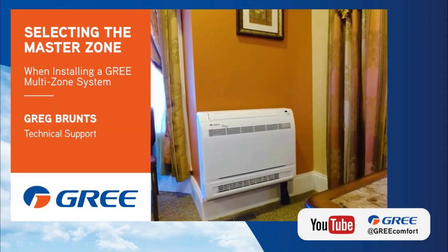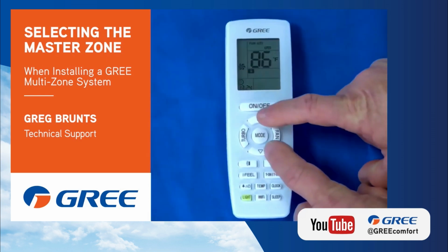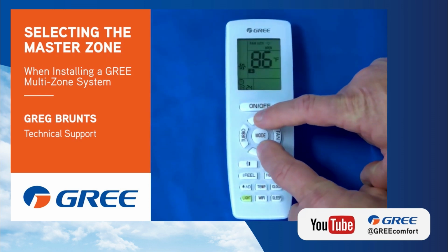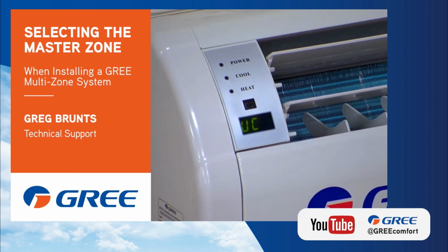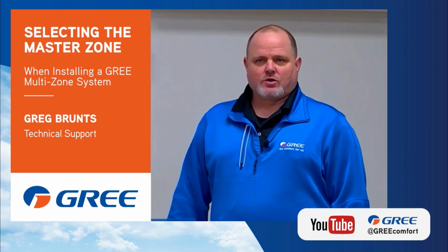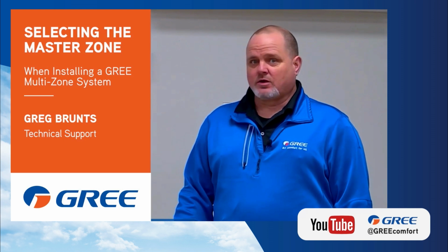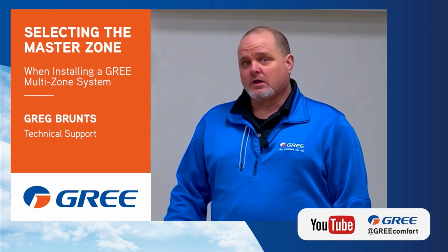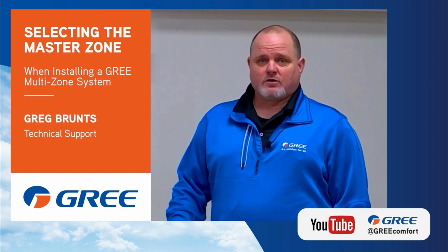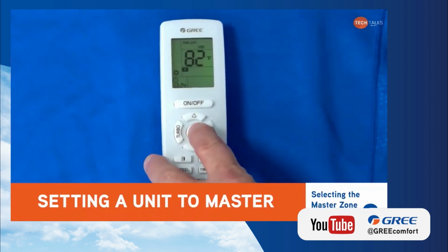I want to show you on the MultiPRO systems, since they auto address, how, for example, on a wall mount, you can change which unit is the master indoor unit. Remember, the master indoor unit is what controls your mode. There is no mode conflict with MultiPRO. In order to set the indoor unit to be the master, first we need to set the mode to fan.